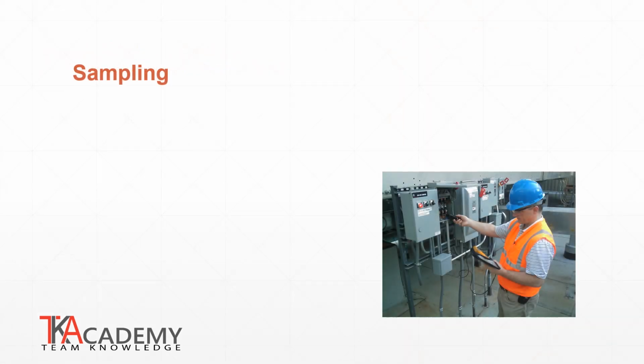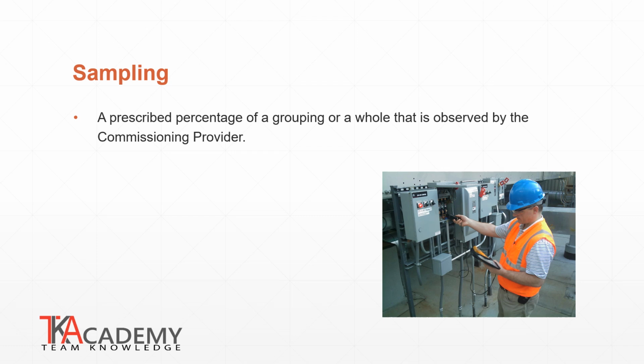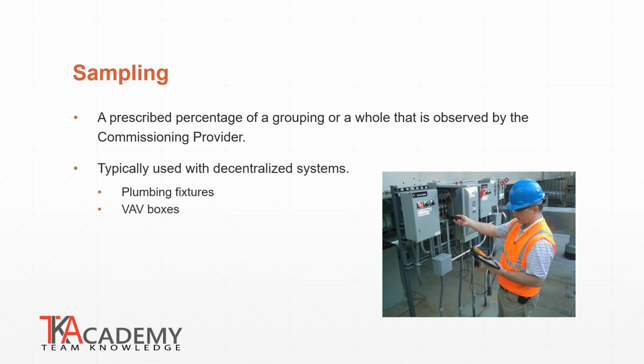It is not reasonable for the commissioning provider to review 100% of the equipment throughout an entire building. In this case, the commissioning provider may conduct a sampling, which is a prescribed percentage of the whole that is observed by the commissioning provider. Sampling may represent a portion of the entire system and offers a representation of the effectiveness of the installation and operation. Sampling is commonly used with decentralized systems such as plumbing fixtures, VAV boxes, heat pumps, and lighting controls.